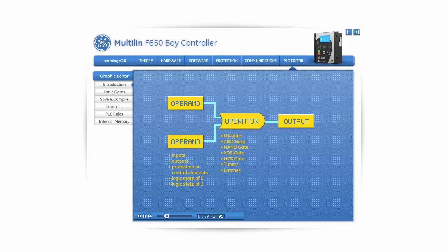A newly manufactured F650 relay already comes with a default PLC configuration built in. It basically combines the various protection function pickups to create a single virtual output that defines all the pickups. The same is done with the operate signals from the protection functions that eventually lead to one signal called the general trip. This default configuration will satisfy the typical user's needs in terms of simple and predictable protection and control functionality. If required, the default logic can also be modified or started again from scratch to meet the requirements of a special application, providing the F650 with extreme flexibility.